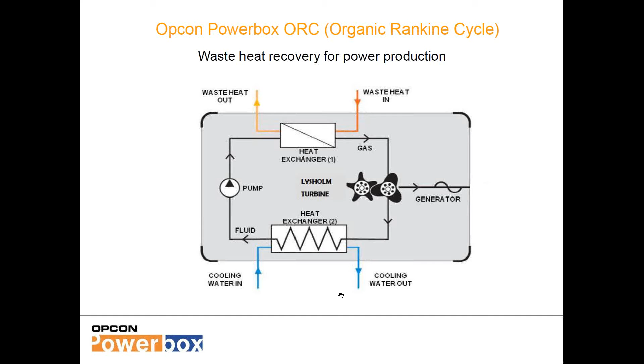So if we are using 70 degrees wastewater on the warm side, we would like to use roughly 20 or 30 degrees cooling water on the cool side. And the cooler it can be, the better, then we will produce more electricity. So this ammonia, it's a closed loop going around like this, with a warm side, with this waste heat, and then the cooling side with the cooling.